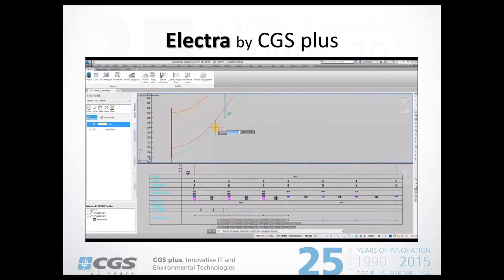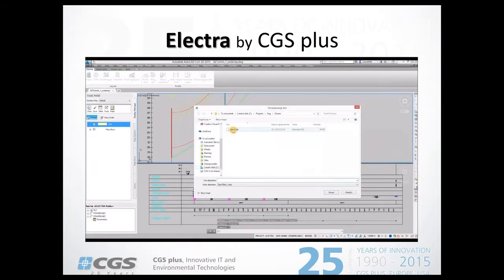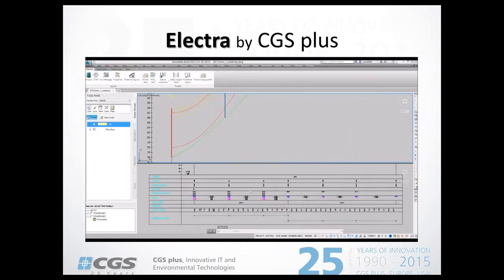so we might need to change the attaching point height on the poles. Then what we can do is also inspect those safety heights between the cables and the terrain and label them in the bands below, and at the end we can produce the report with all the sags containing all the data for all cables that were used, all the temperatures and the sags which occur at specific temperatures of the air.